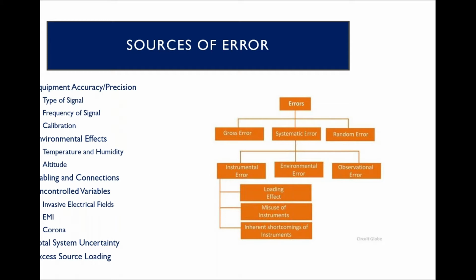There are a wide variety of sources which could influence your ability to make accurate measurements. Starting with the equipment that you're using, every single piece of equipment will likely have some sort of influence on the accuracy or the precision of your measurement. A lot of these will be influenced by what type of signal you're measuring, whether it's AC or DC, the frequency of the signal if it is an AC signal, as well as the calibration and the uncertainties of the calibration on that piece of equipment. This also takes into consideration if you have multiple pieces of equipment in line: you have to at least consider the error of each of those pieces of equipment as a whole.